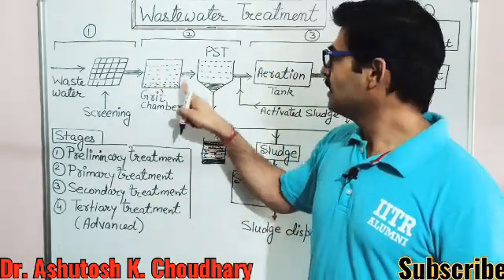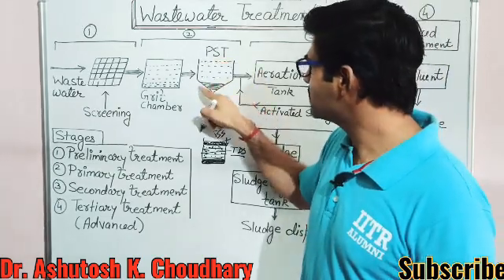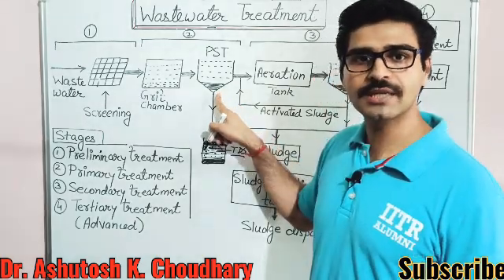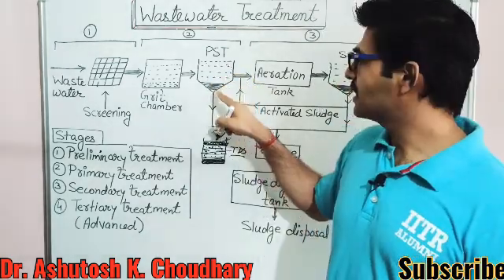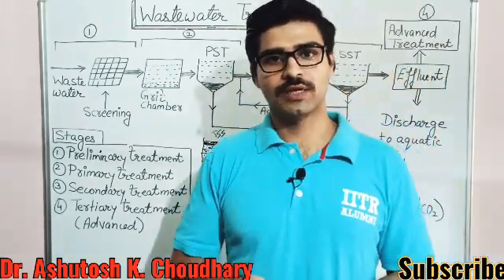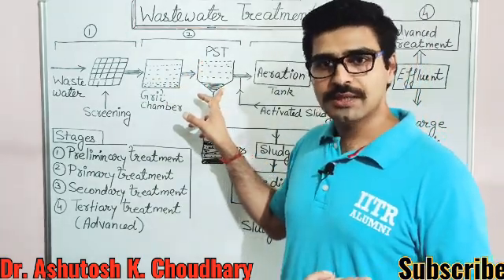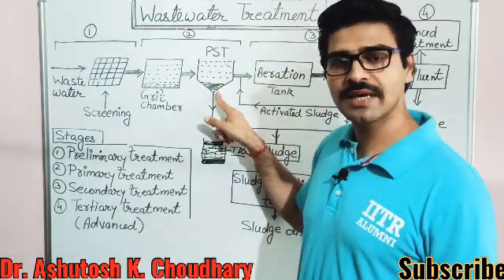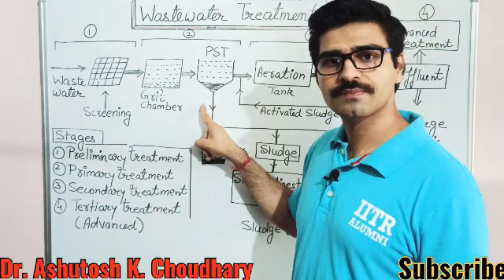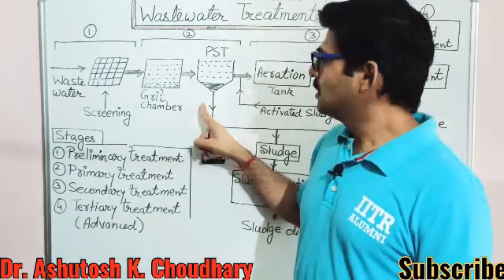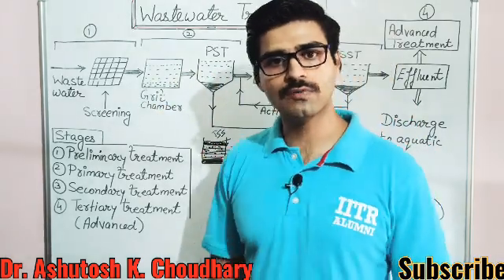Next is the PST — primary sedimentation tank. The primary sedimentation tank is generally conical in shape at the bottom. With time, some fine particles get settled under the influence of gravity. These settled particles form what is known as sludge. This step is primary treatment — removal of suspended particles from the water.